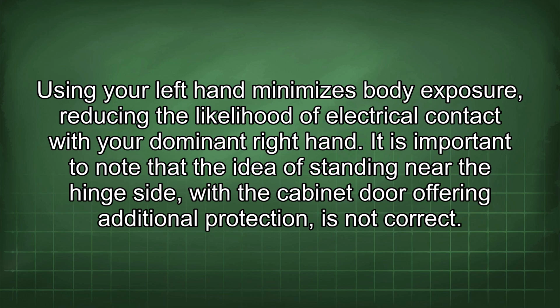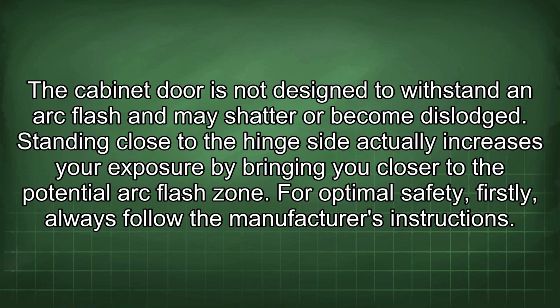It is important to note that the idea of standing near the hinge side, with the cabinet door offering additional protection, is not correct. The cabinet door is not designed to withstand an arc flash and may shatter or become dislodged. Standing close to the hinge side actually increases your exposure by bringing you closer to the potential arc flash zone.